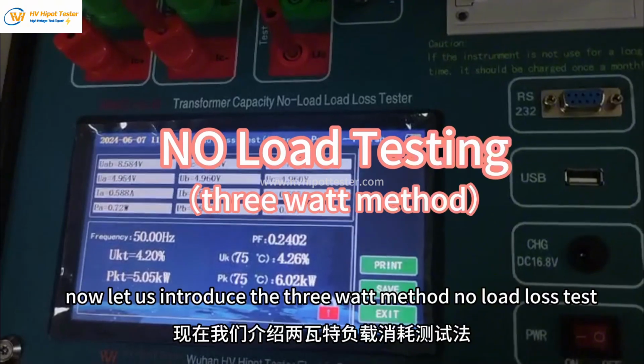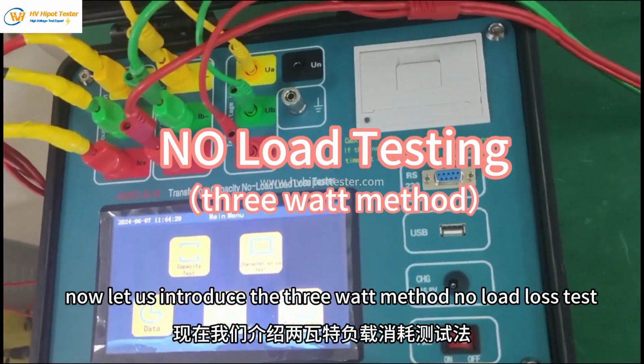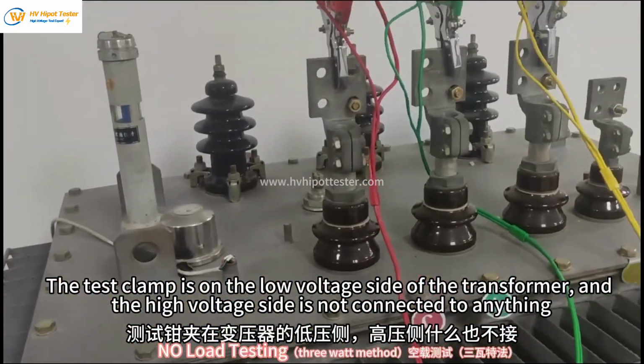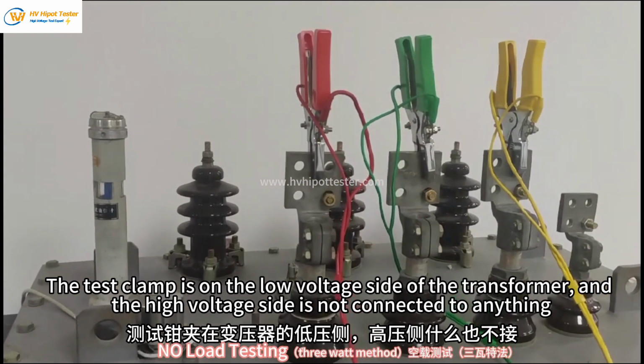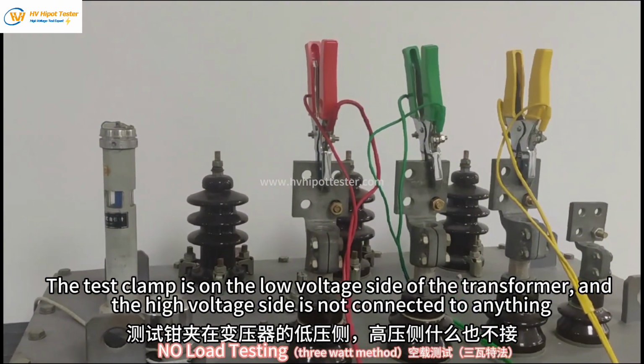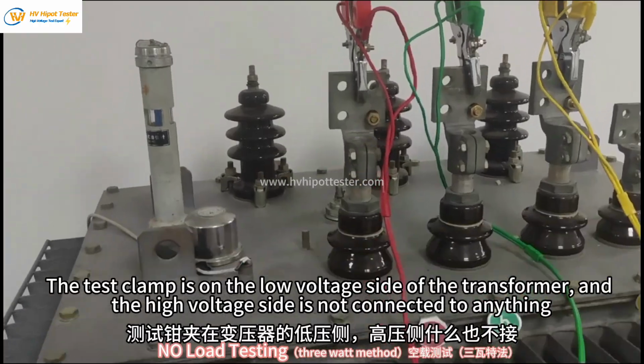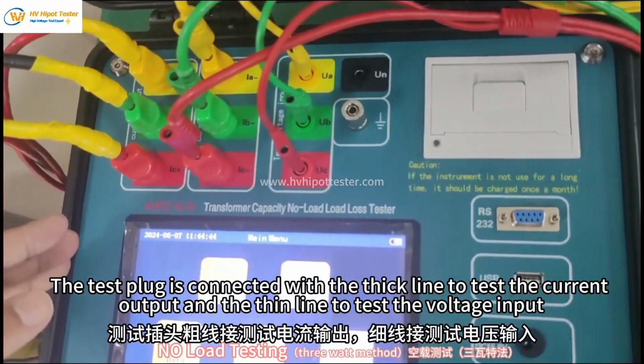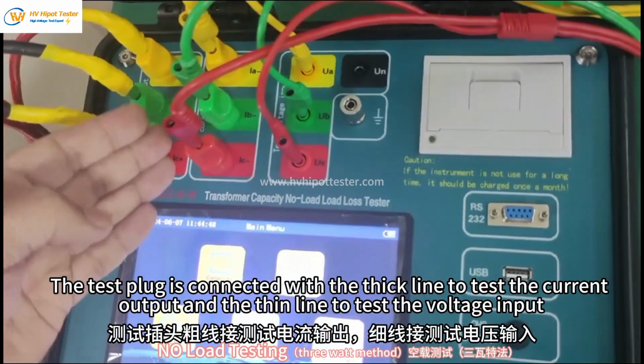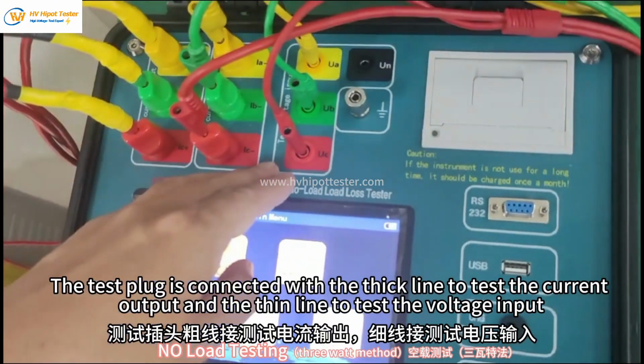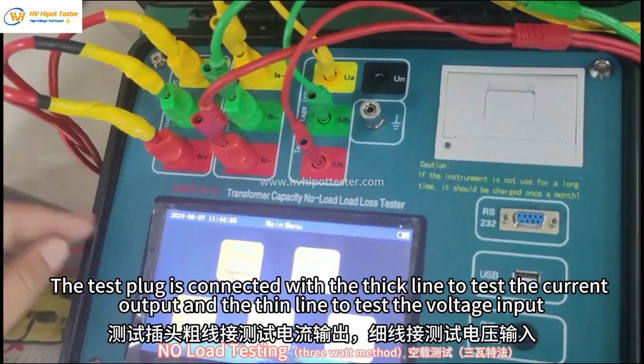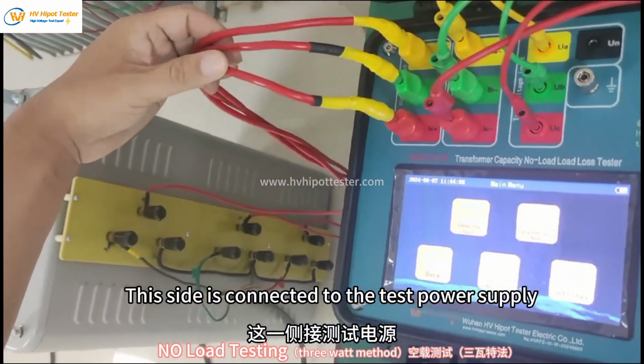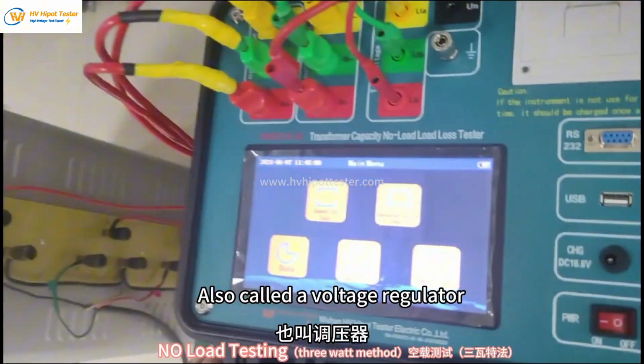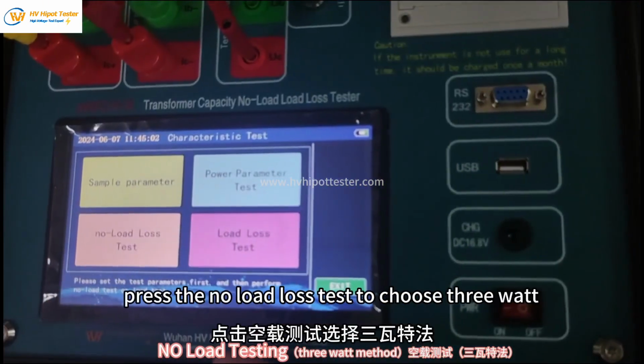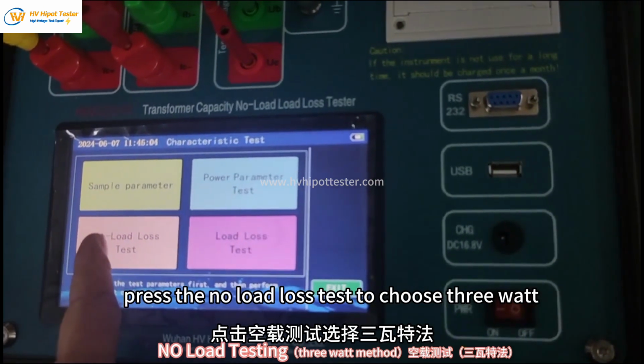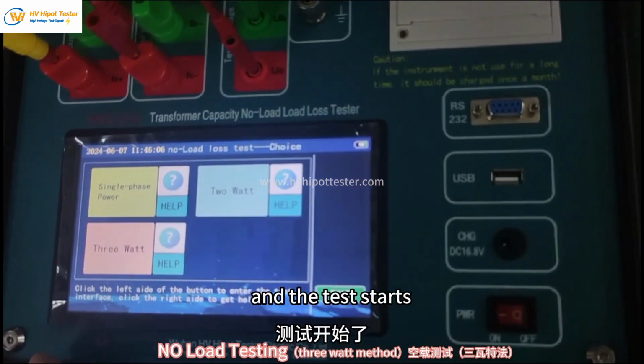Now let us introduce the 3-watt method no load loss test. The test clamp is on the low voltage side of the transformer and the high voltage side is not connected to anything. The test plug is connected with the thick line to test the current output and the thin line to test the voltage input. This side is connected to the test power supply, also called a voltage regulator. Press the no load loss test, choose 3 watt, and the test starts.